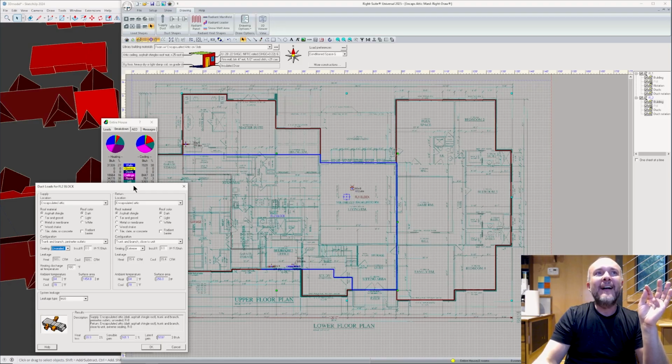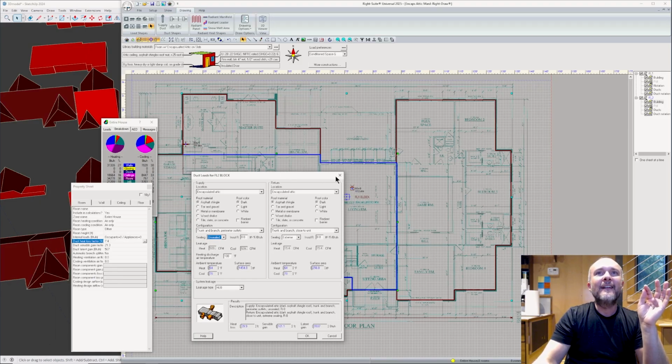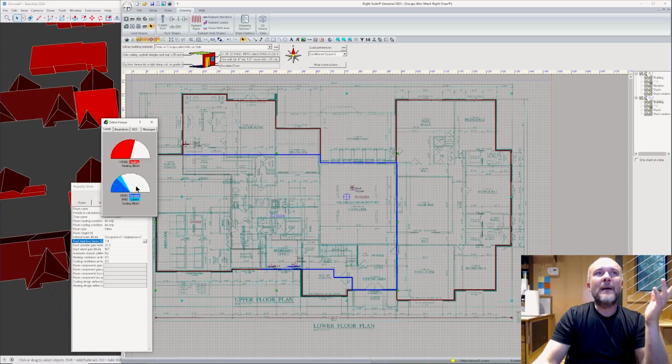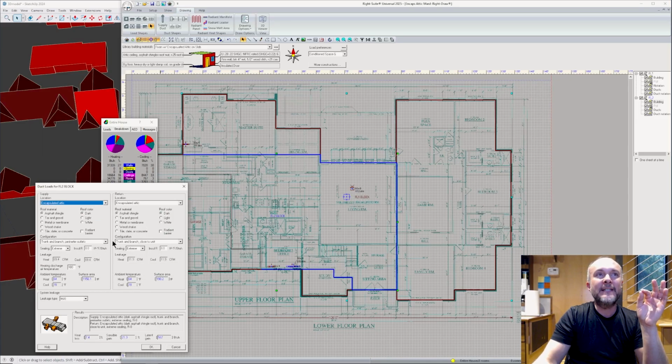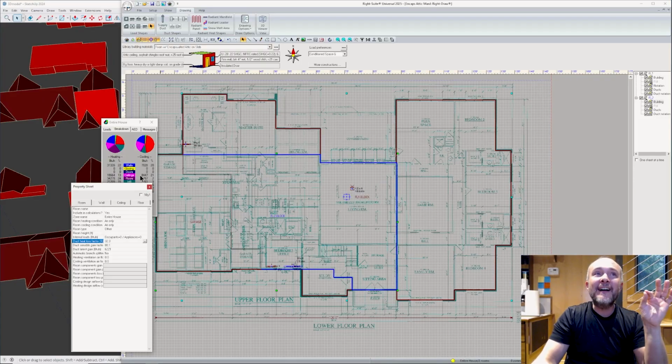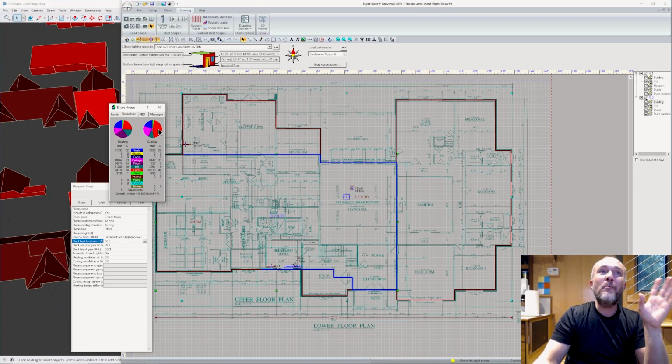We're starting with a total of about 34,500 cooling, 115,000 heating, and the ducts being 7% and 17% of our total load, respectively, per season. If we now unseal these things, because, oops, the guy didn't come that day, and no one's ever going to find out about this because we're not going to test it because it's not required by code. Now, the duct leakage in the summertime is almost 50%, and in the wintertime, it's gone up to 25%.